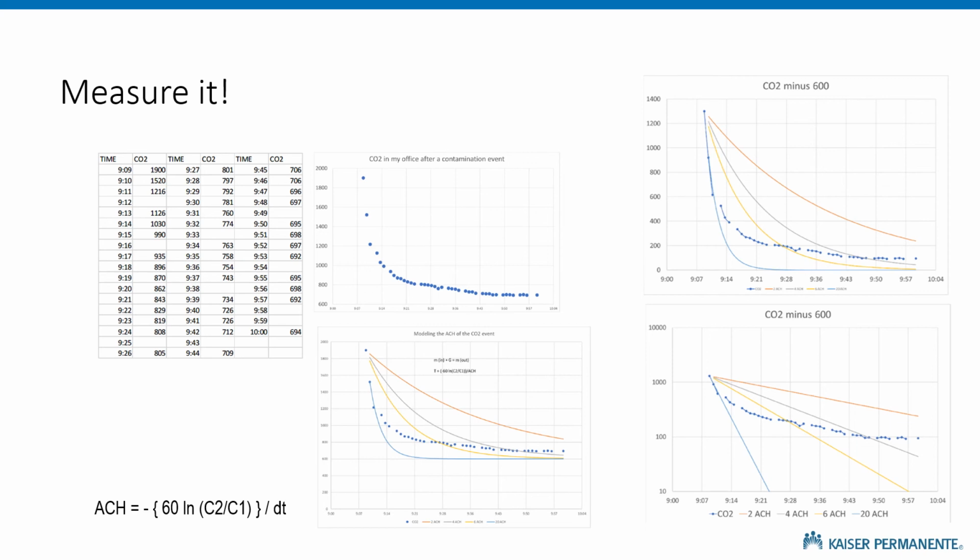But then it trails off again, and it trails off to like a half of an air change. And I was actually really surprised how long that last bit of contamination stayed in the room. This is with the door closed. And eventually I just kind of got up and went and got a donut. But it brings up this interesting idea that we could see sustained or sustainable low differential concentrations across a closed door like this that never resolve or take a long, long, long time to resolve, much longer than our equations would predict. I think that's worth more investigation.